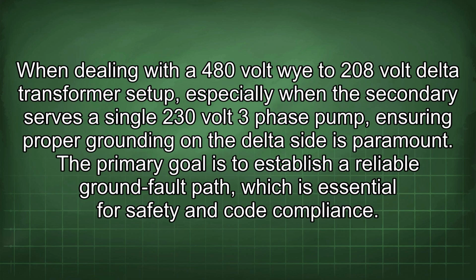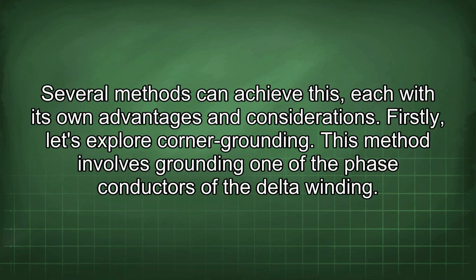When dealing with a 480-volt Y to 208-volt delta transformer setup, especially when the secondary serves a single 230-volt three-phase pump, ensuring proper grounding on the delta side is paramount. The primary goal is to establish a reliable ground fault path, which is essential for safety and code compliance. Several methods can achieve this, each with its own advantages and considerations.